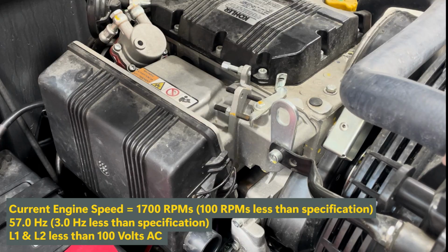On this specific light tower, this engine speed is 1700 RPMs. Our hertz reading is around 57 hertz, and our voltage output out of L1 and L2 is less than 100 volts.